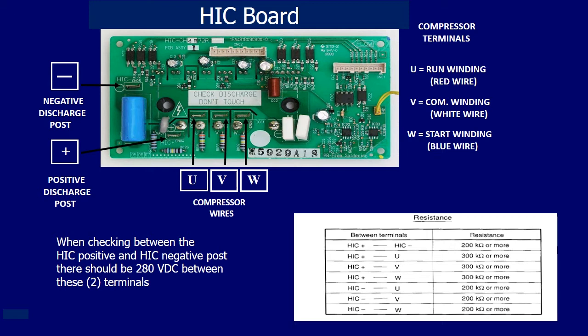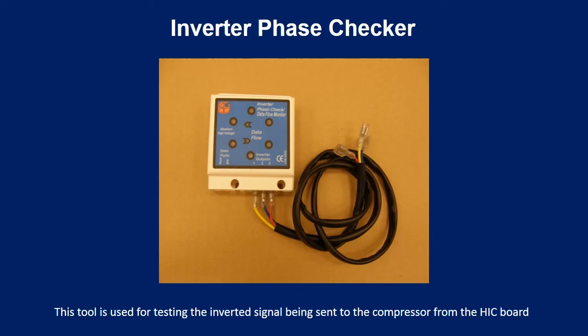Also, with power supplied to the system, there should be 280 volts DC or higher present across the HIC positive and HIC negative terminals. This tool, referenced as an inverter phase checker, can also be used to verify if the inverted signal from the HIC board to the compressor is good or not. This tool can be purchased through most HVAC supply houses.